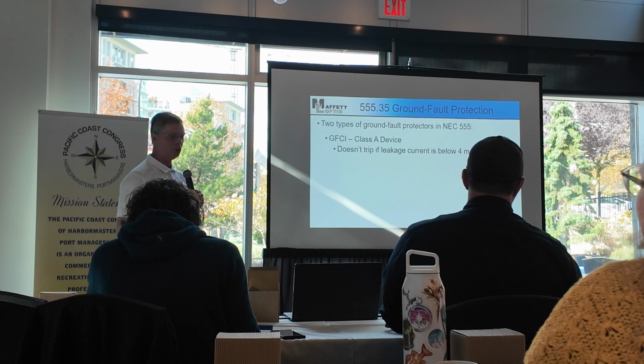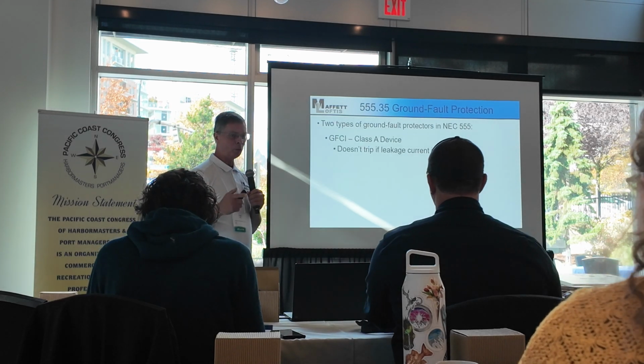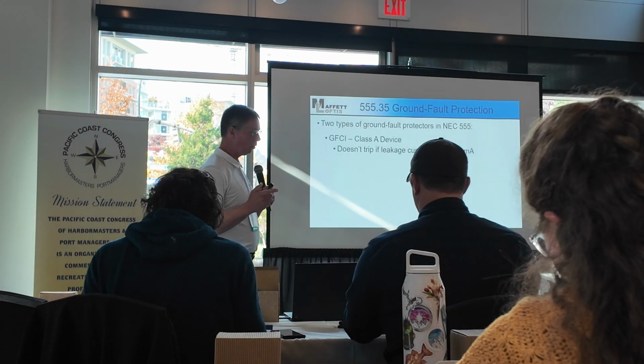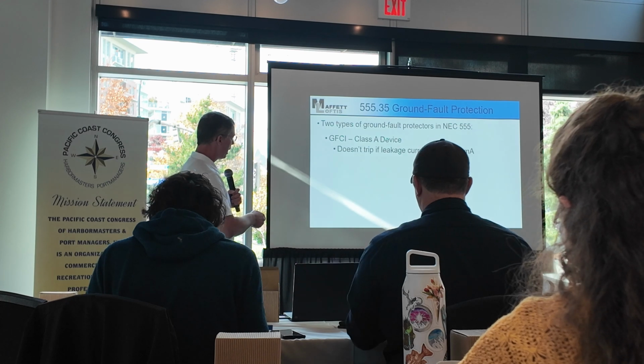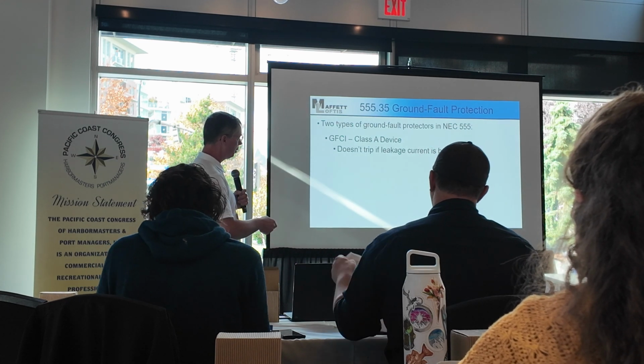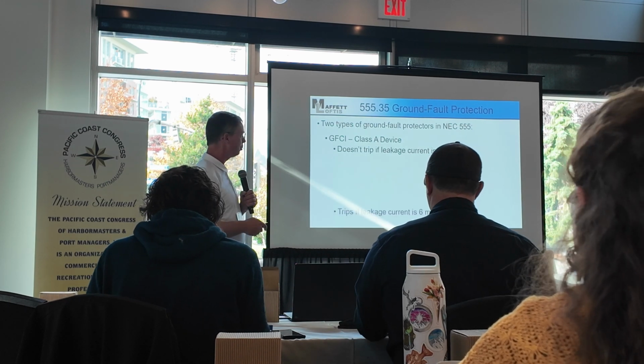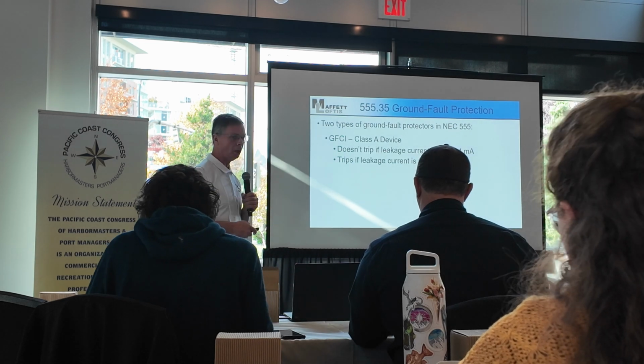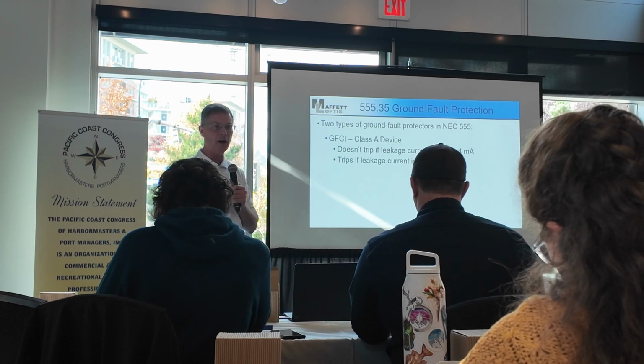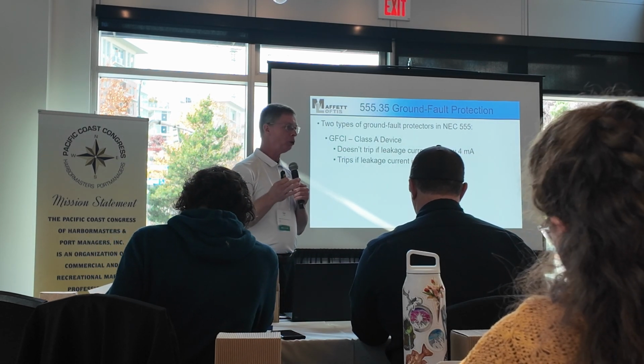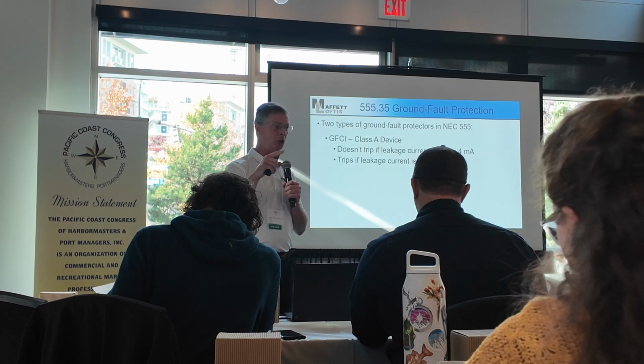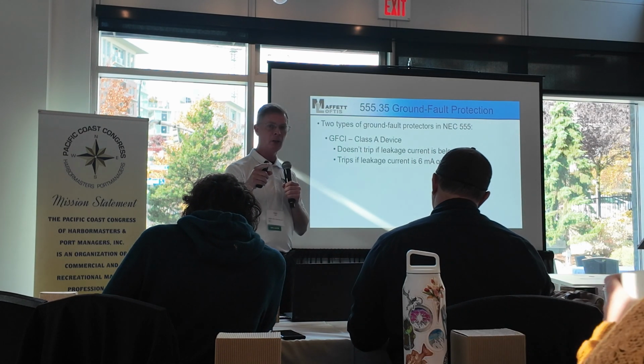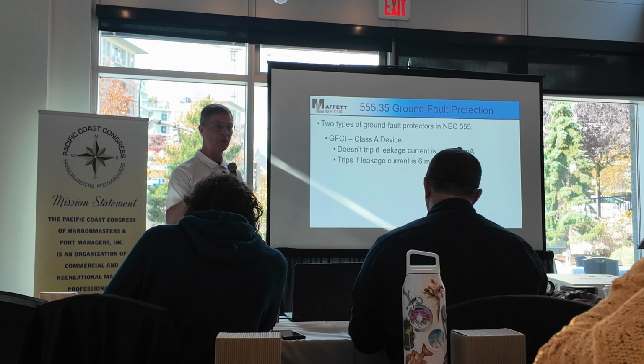Well, there's two types of GFE. I'm not going to get into everything that I wanted to do, but I wanted to at least do this. There is the Class A device, GFE, which is not supposed to trip below 4 milliamps and will always trip above 6. So 4 to 6 milliamps is a Class A device. It's the same device that you have in your bathrooms, with a test and reset button, in your kitchen countertops, outside, any location in your house. This is the GFCI.